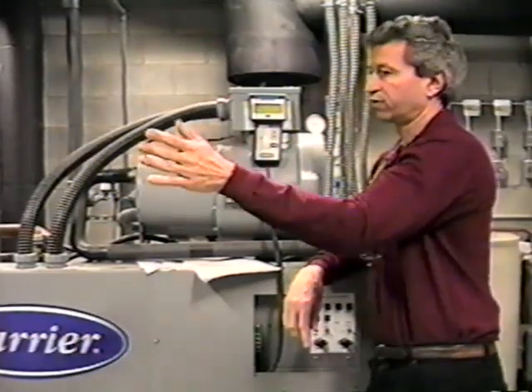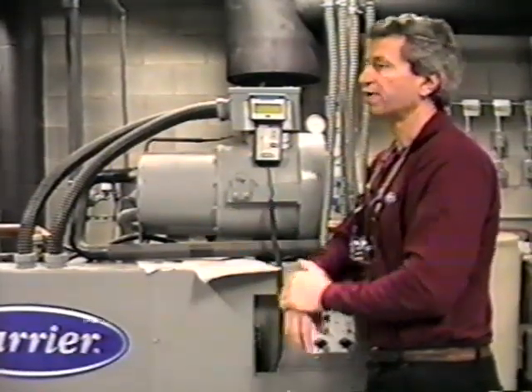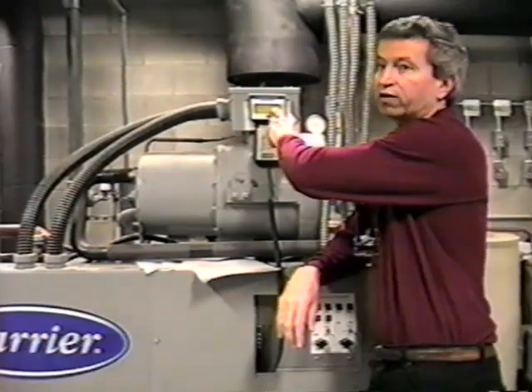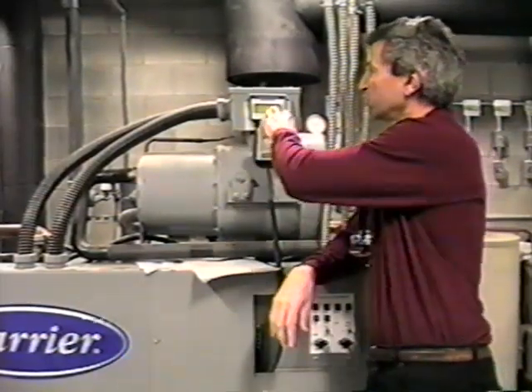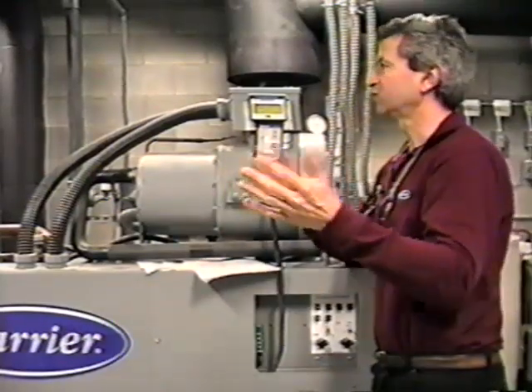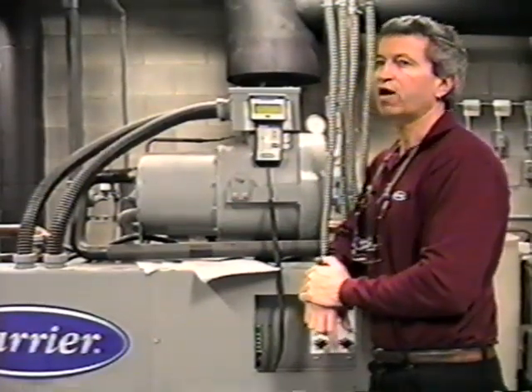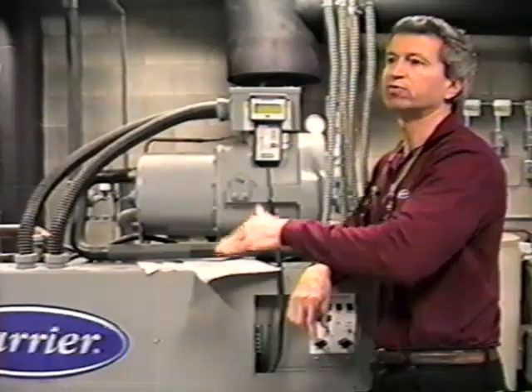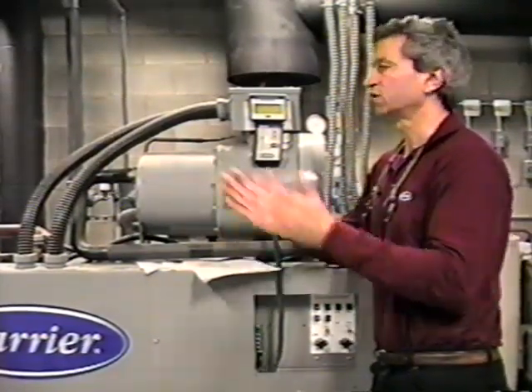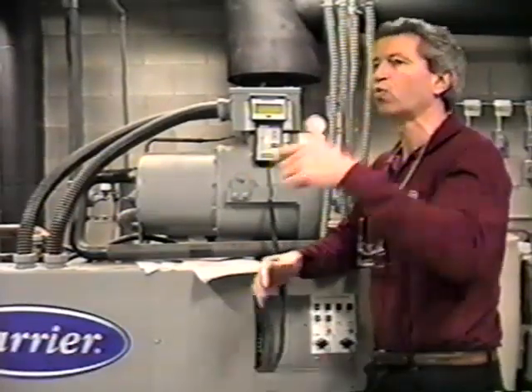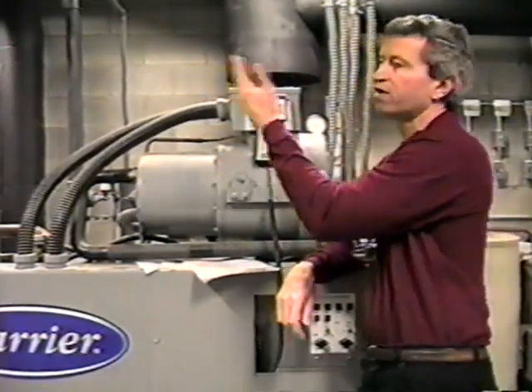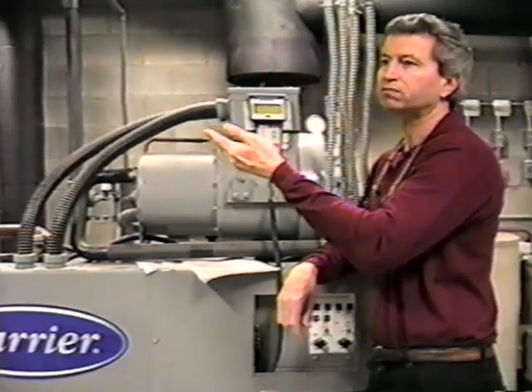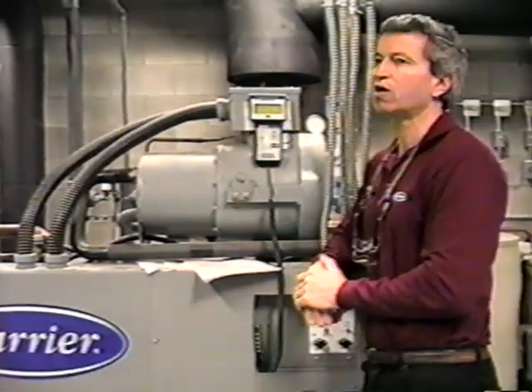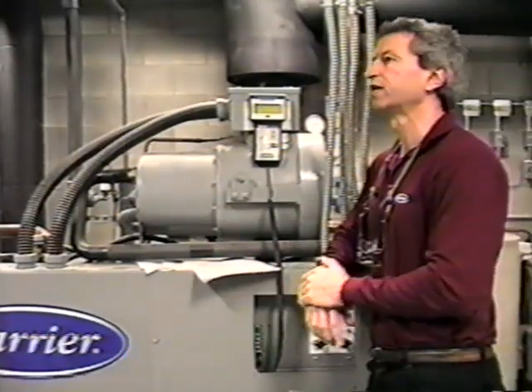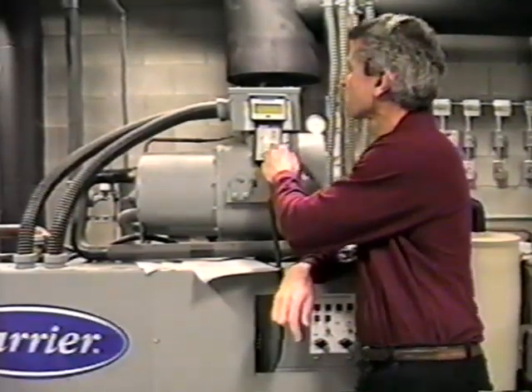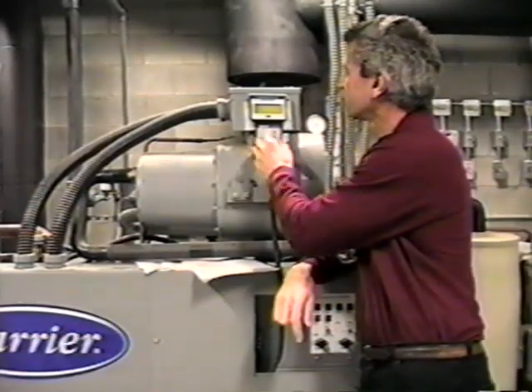If you'll notice, one of your items on the log sheet is that level in the cooler. You may not see that exactly at 1.8 all the time. It's going to fluctuate, and it's also going to be reset based on some other internal parameters that are going on in the machine. So it may be reset up and it may be reset down, again, depending on what's going on. It tries to compensate for varying conditions within the system. So that number may be 2.0, 2.1, again, depending on how soon after startup it is, how stable a load is, and things of that nature. And that's it for that menu.